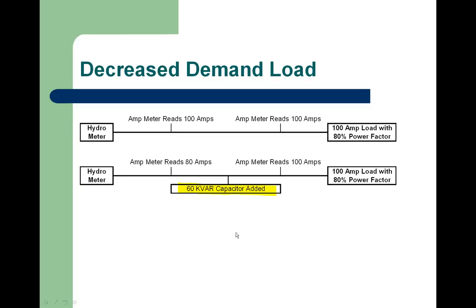And if we take a capacitor bank, in this particular case, a 60 kVAR capacitor bank highlighted here, and we added that to some portion in the facility, and we use a motor as an example, perhaps a 100 horsepower motor, and connect our amp meter between the load and where the capacitor bank was connected, we would read 100 amps. Now, if we move the meter up between wherever the capacitor bank was connected and the hydro meter, our amp meter would actually read about 80 amps.